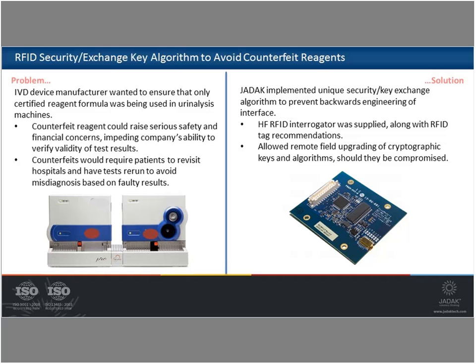An RFID tag protected by advanced cryptographic protocols was placed on the reagent bottles, and then calibration information was encoded into it and read by the machine when the reagent bottle was installed. The doses that were used were counted and written to the tag so that when the bottle was empty, the bottle couldn't be reused. The counting system was also used to warn the user when the reagent bottle was nearly empty. And in the unlikely event that a third party discovered the cryptographic key and started cloning the tags, both the keys and the cryptographic algorithm itself could be field upgraded if necessary.